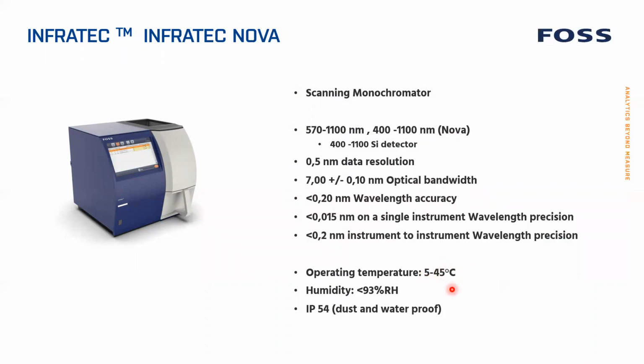Operating temperature goes from 5 up to 45 degrees. Some people claim they have very hot environments. I would not like to work in that kind of environment when it's above 40, but that may be the case in some places. Humidity is less than 93 relative humidity, and this is IP54, so it's dust and waterproof. It's a little open because the connectors and things like that are not special, but it's so well protected that any dust or water coming into the instrument will not have any effect on the performance of the instrument.